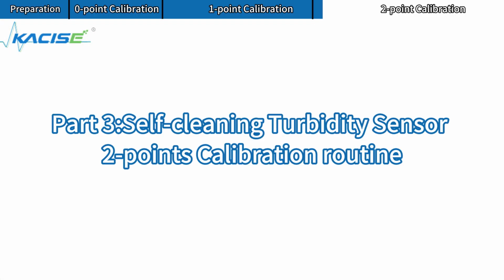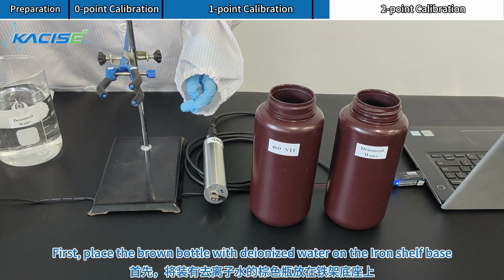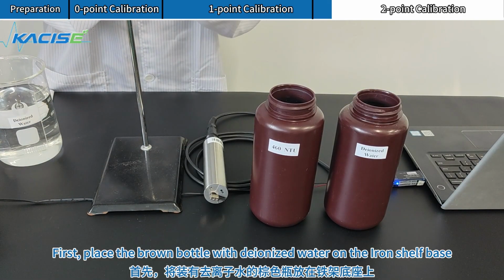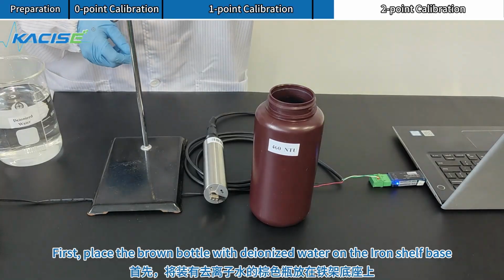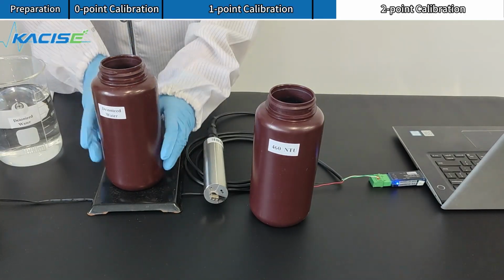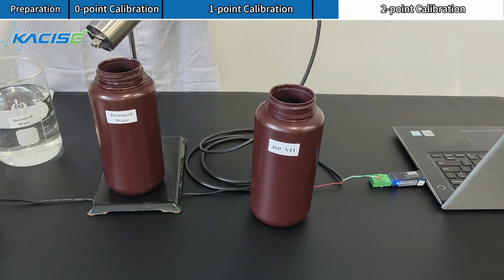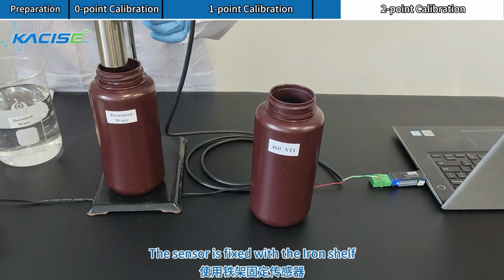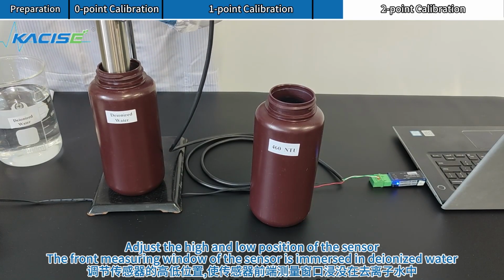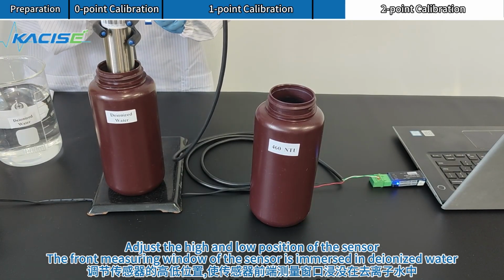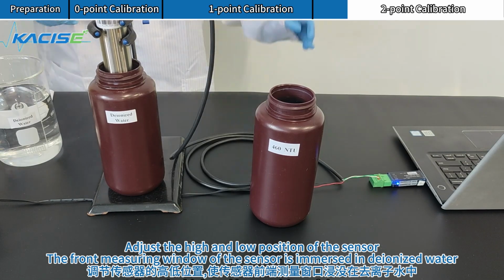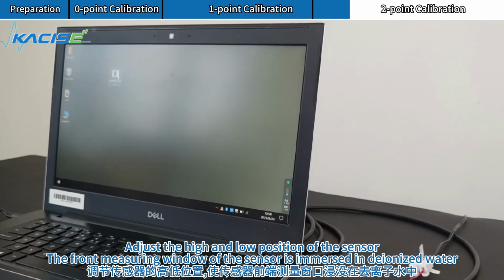Part 3. Self-cleaning turbidity sensor. 2 points calibration routine. First, place the brown bottle with deionized water on the iron shelf base. The sensor is fixed with the iron shelf. Adjust the high and low position of the sensor. The front measuring window of the sensor is immersed in deionized water.